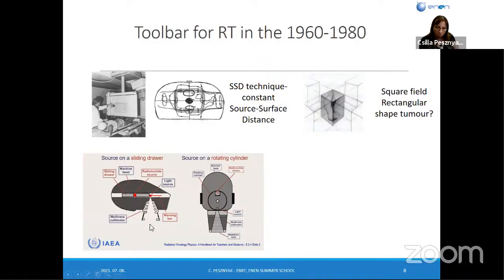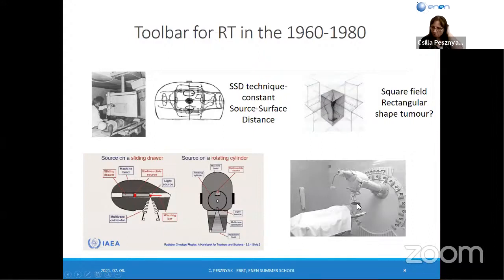But here you can see the construction of the cobalt unit. Here is the cobalt unit in a storage position, here when it's irradiating, and it's a big shielding of the head, and this part is the collimator part. In the storage position, and when we would like to irradiate the patient, the source has to be put in this position. There is another, this is a source on a rotating cylinder, in a storage position, and when we would like to irradiate the patient, it can turn down, and in this case, using the collimator system, we can irradiate. It was the first rotating cobalt unit in Hungary made by the Hungarian company. You can see here the table, the patient, and the cobalt unit can turn around the patient, and we can also change the field size.